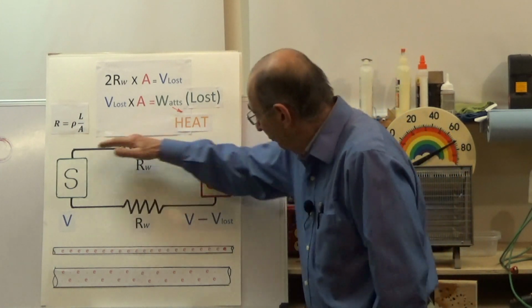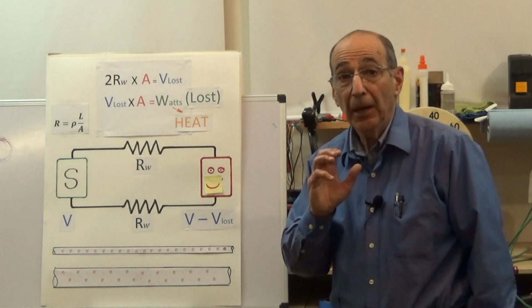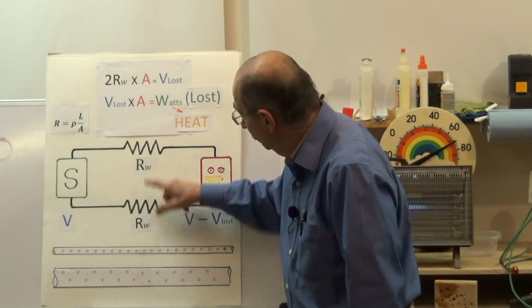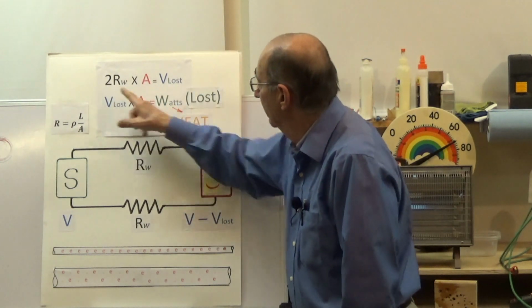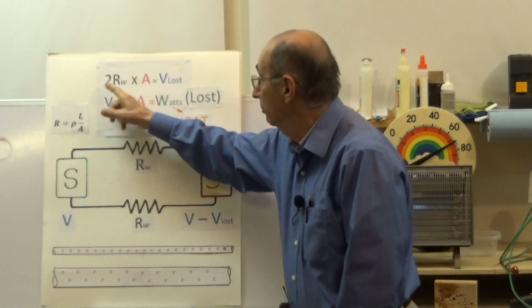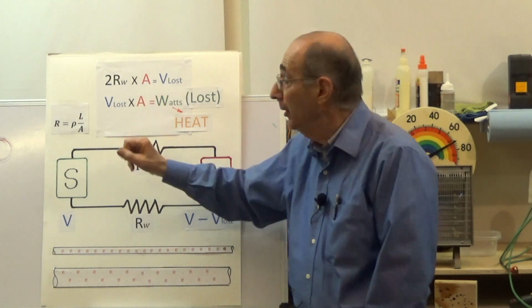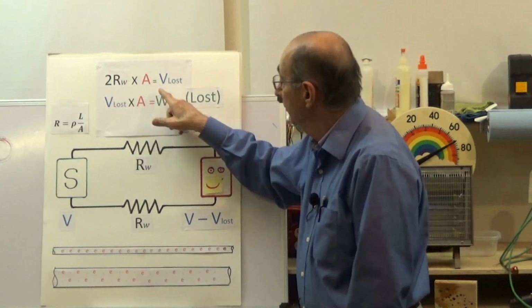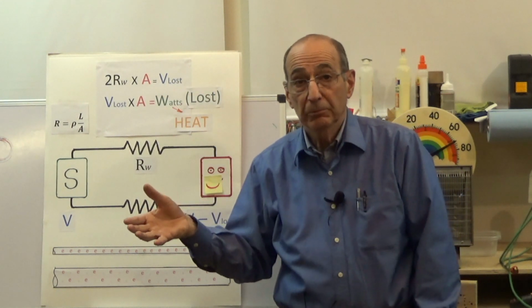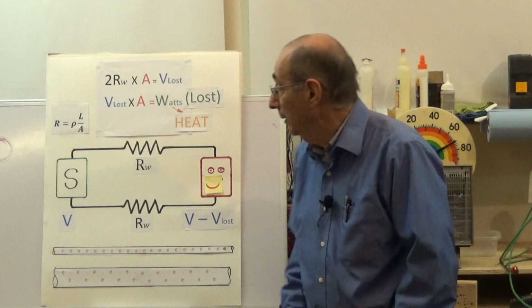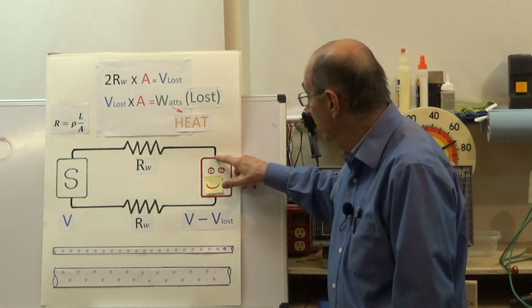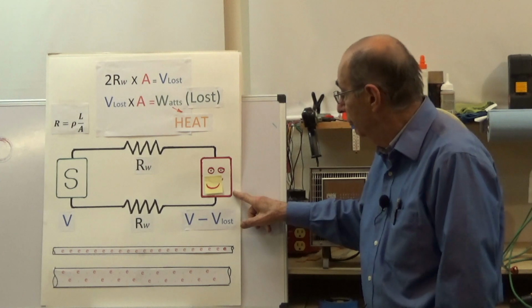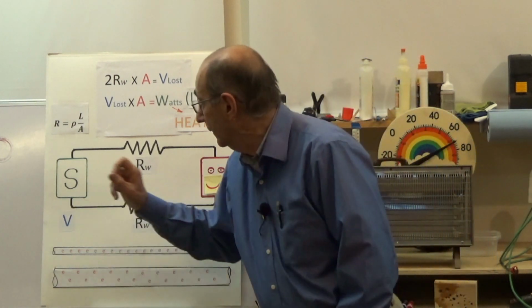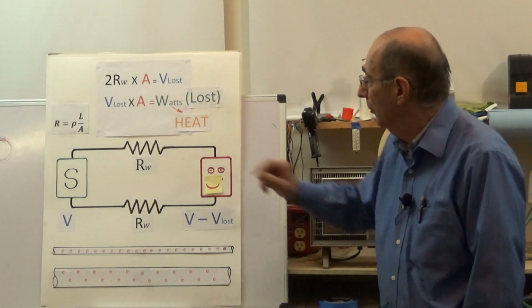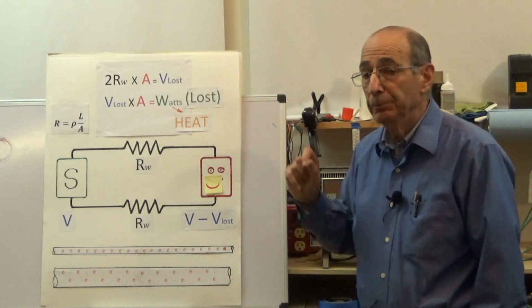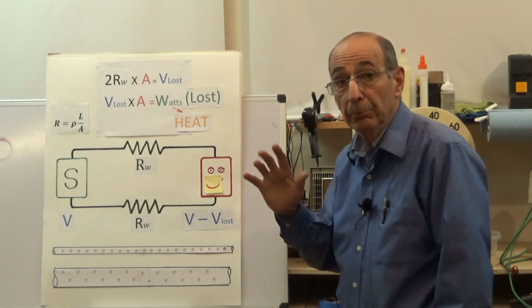Now when we run amperage through that resistance, something happens. Because I have two of them, you'll notice in this formula I have 2 RW. I could put RW plus RW, or I can put 2 RW. 2 RW times the amps equals the voltage that's lost. It's wasted, used up moving the electrons from the source to my device and back. So we already have a problem here - voltage is being used up. Hopefully it's a very small amount, but we can't count on that.